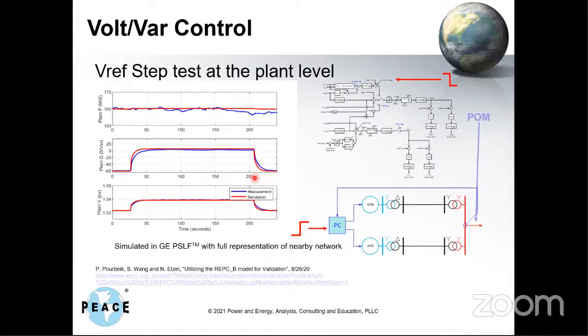Here's a real life example of a voltage step test on a large wind plant with maybe 100 turbines distributed through a collector system. One grouping is on one large substation transformer, the other on another, and there's an overall power plant controller controlling all these wind turbines. We asked to change the voltage at the POI with a step change, and it did. We stepped it back, and the blue is measurement.